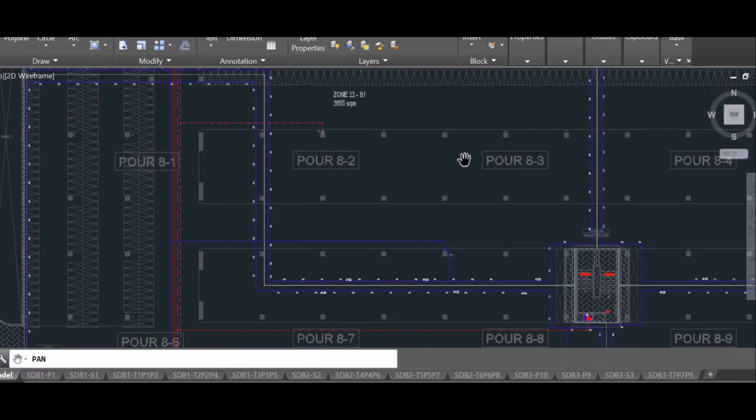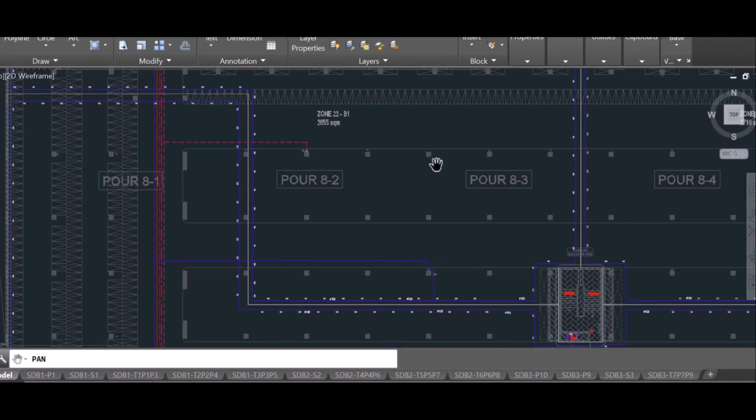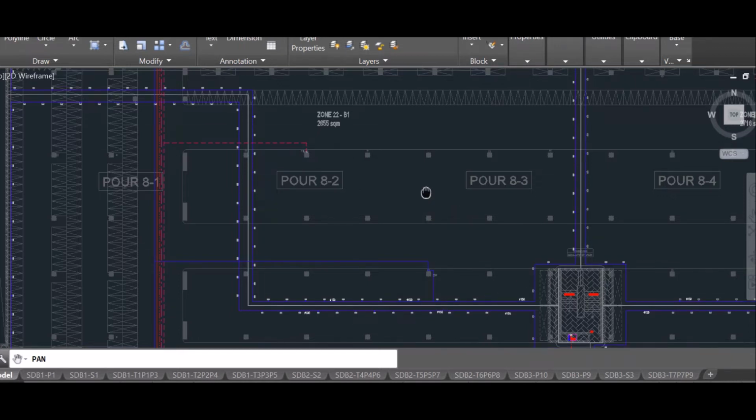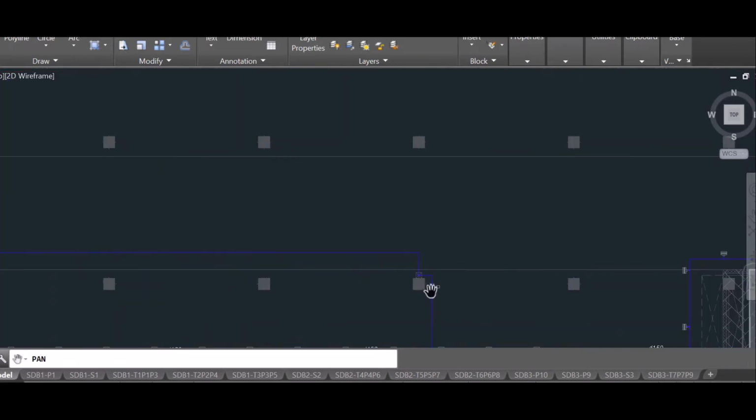While a fire occurs within this zone, the sensor also installed within this zone will sense the fire and send it to the fire alarm panel, and from the panel it will get the signal, and then it will actuate and release the water, and the water will flow through the nozzle, and it will create a water barrier and restrict the fire. This is the main function of this deluge valve.